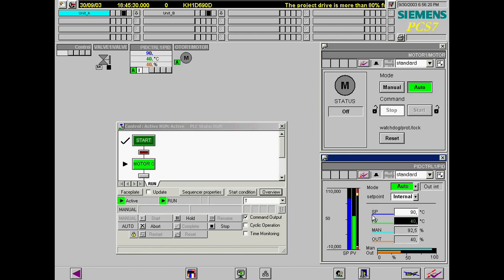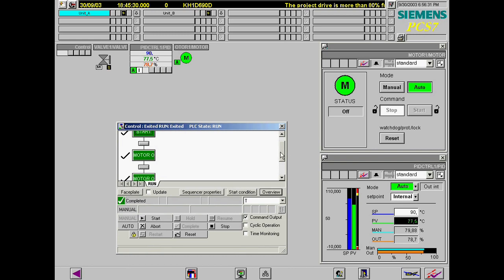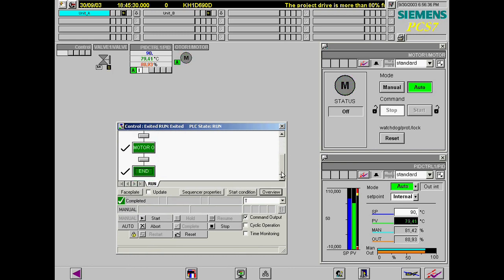The sequence will now run through to completion. Motor 1 will be started in the third step of the sequence and be switched off again in step 4, after the configured step duration time of 10 seconds has elapsed.